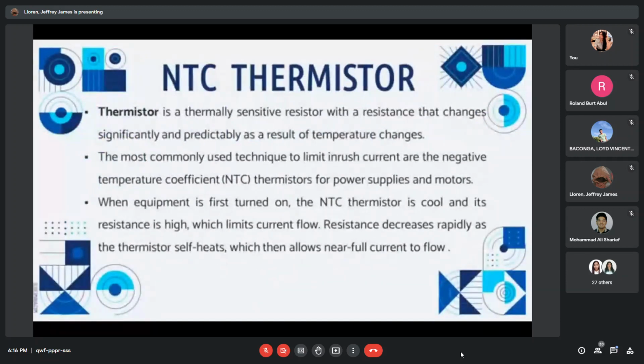NTC thermistor. So what is a thermistor, by the way? A thermistor is a thermally sensitive resistor with a resistance that changes significantly and predictably as a result of temperature changes. The most commonly used technique to limit inrush current is the negative temperature coefficient or NTC thermistor for power supplies and motors. So when equipment is first turned on, the NTC thermistor is cool and its resistance is high, which limits current flow. Resistance decreases rapidly as the thermistor self-heats, which then allows near full current to flow.